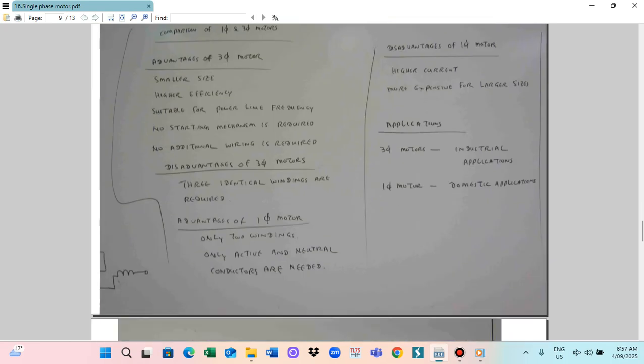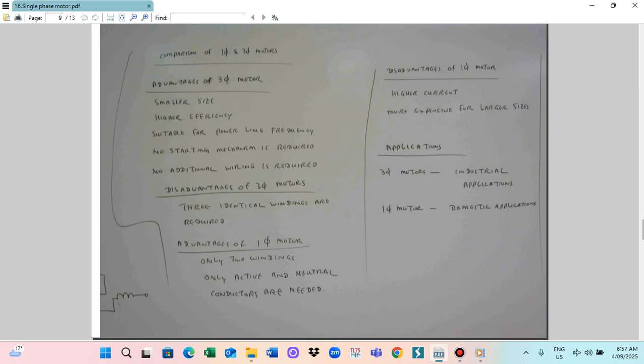Next topic is a comparison of the single-phase and three-phase motor. Especially, the three-phase machines have the advantage because they are smaller. With the same power rating, three-phase machines are smaller and more compact. They provide higher efficiency and are also superior for the power line frequency. No starting mechanism is required, and no additional wiring is required. These are the characteristic advantages of the three-phase induction motor.